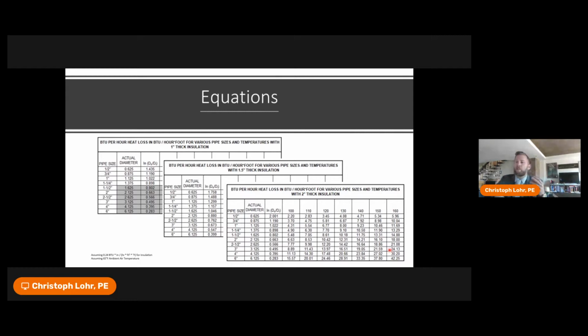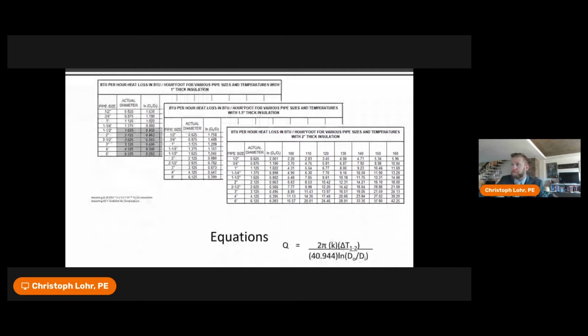So really getting the right assumption for a BTU per hour per lineal foot heat loss is step one. Again, I made some assumptions on insulation and temperature. That's part of the slides there. And these charts will hopefully be in the ASPE Legionella Design Guide, and this methodology will hopefully be captured in the ASPE Legionella Design Guide that will hopefully be released for public review at some point this year.